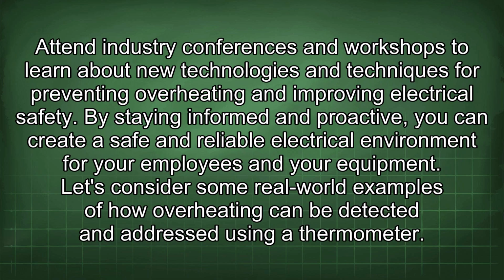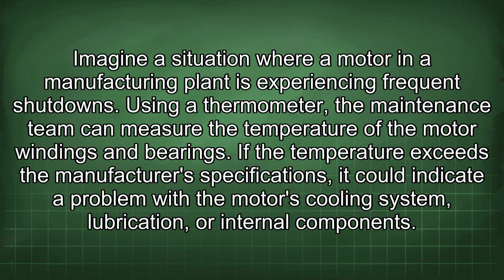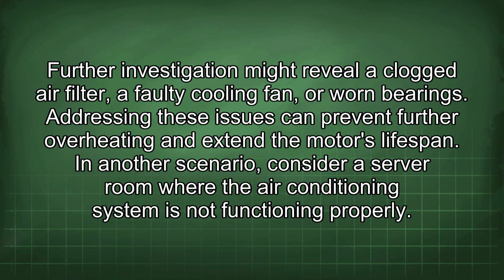Attend industry conferences and workshops to learn about new technologies and techniques for preventing overheating and improving electrical safety. By staying informed and proactive, you can create a safe and reliable electrical environment for your employees and your equipment. Let's consider some real-world examples of how overheating can be detected and addressed using a thermometer. Imagine a situation where a motor in a manufacturing plant is experiencing frequent shutdowns. Using a thermometer, the maintenance team can measure the temperature of the motor windings and bearings. If the temperature exceeds the manufacturer's specifications, it could indicate a problem with the motor's cooling system, lubrication, or internal components. Further investigation might reveal a clogged air filter, a faulty cooling fan, or worn bearings. Addressing these issues can prevent further overheating and extend the motor's lifespan.